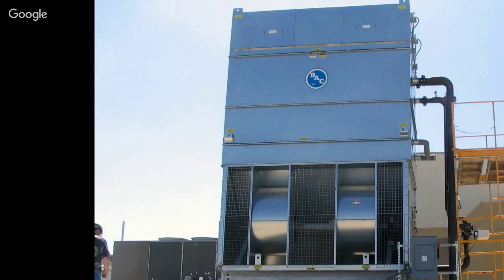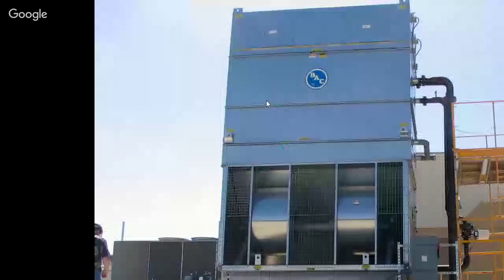Should have it back. So to back up, the biggest lesson learned when it comes to process cooling, and I just dealt with this yesterday with one of my engineers, is that laboratory equipment manufacturers have been so used to using tap water at high pressure, 80 psi in buildings, and they don't care what the return pressure is because they're just going to the drain. So for us engineers, we need to know how much pressure differential your laboratory piece of equipment requires.